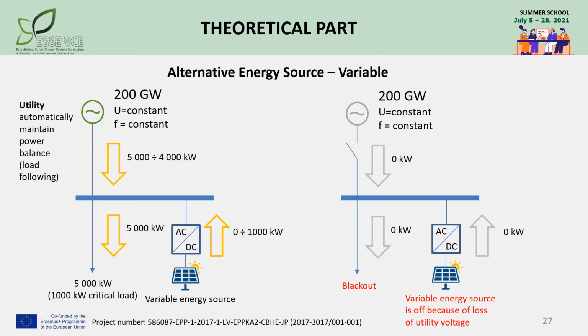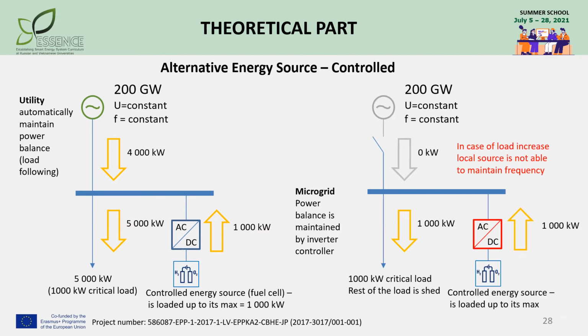And even if we have a more expensive grid forming inverter used for connecting the variable energy source, the output of the variable energy source doesn't allow adequate system balancing and stable operation of the system because it changes in respect to the weather conditions. In case of a controlled alternative energy source like fuel cells with a grid forming inverter, the drawbacks are the same as for a conventional generator loaded up to its max output, except for much higher capital costs.